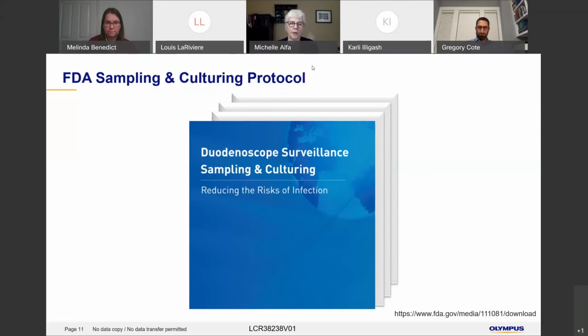Part of the issue was that there was no standardized approach to, number one, sample collection, and no standardized approach to the culture methodology. And as a clinical microbiologist, there's a couple of points that came out in this that I think were really very, very germane. The sensitivity of the culture sample collection methodology is one thing. So how efficient is your sample collection protocol? Are you flushing sterile water or buffer down the instrument channel? Are you doing a flush, brush, flush protocol? So the sensitivity of the sample collection protocol is important.